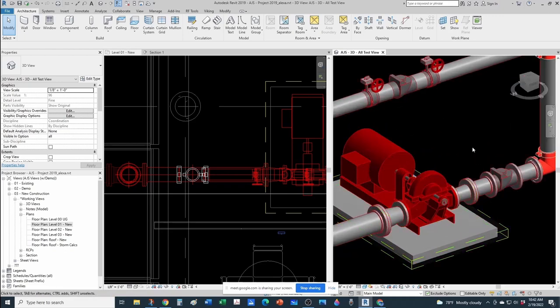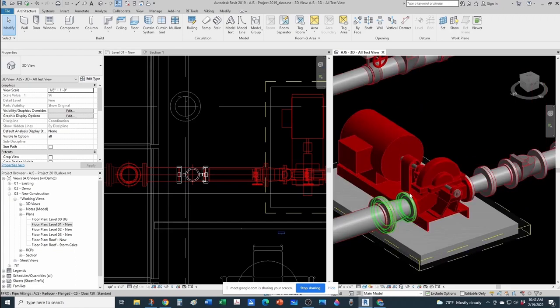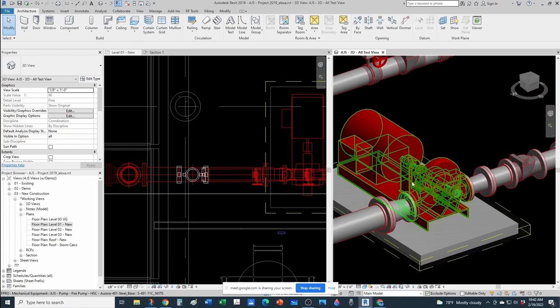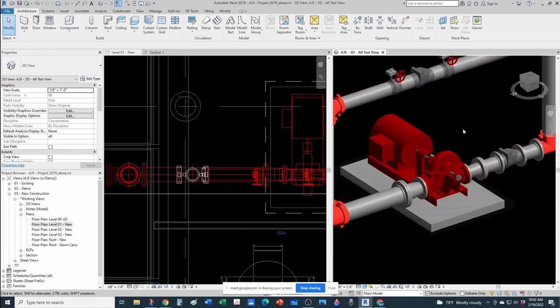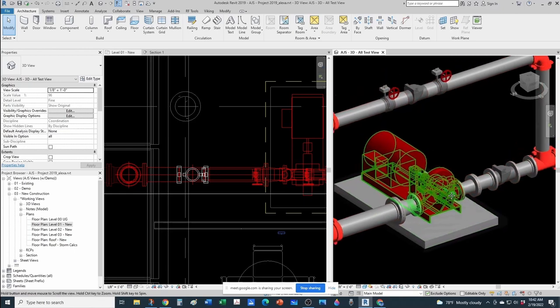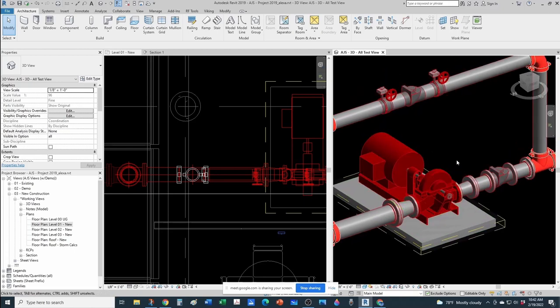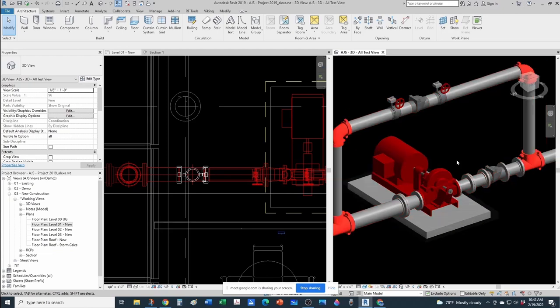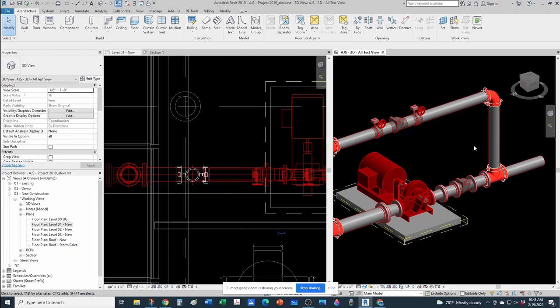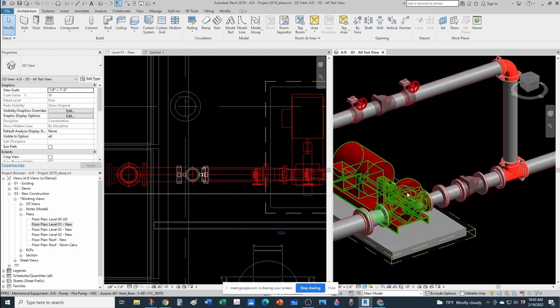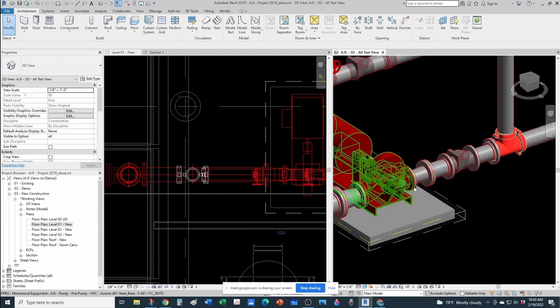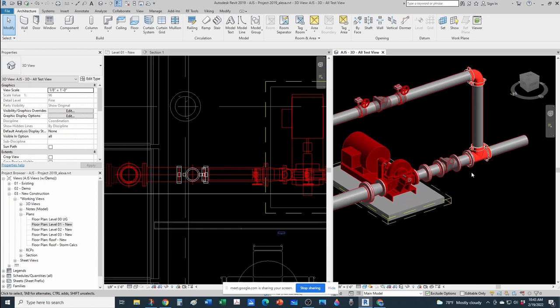At the beginning of the presentation, I was talking about the suction pressure gauge and the discharge pressure gauge and the air release valve at the top of the casing. All that, we're not going to model, because you typically put that in a detail and have the contractor provide it. But we'll try to be as accurate as possible at our level of development for consulting engineering. So at the discharge of your pump, depending on your discharge flange size, you may need an increaser to go to the required discharge pipe size per NFPA 20.